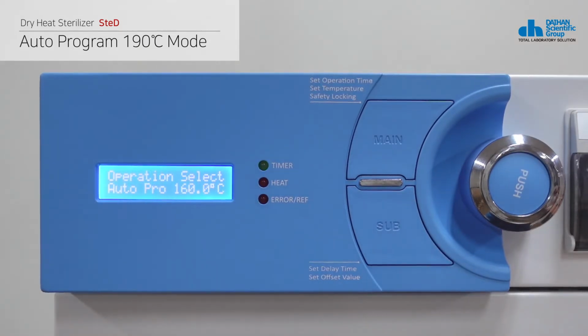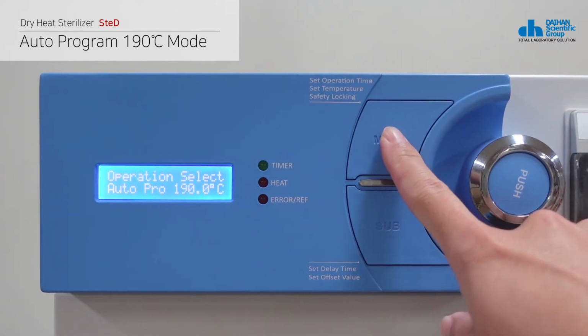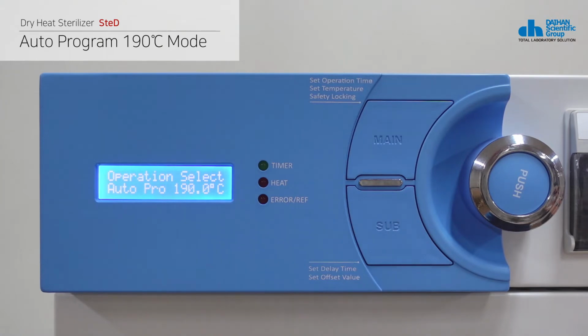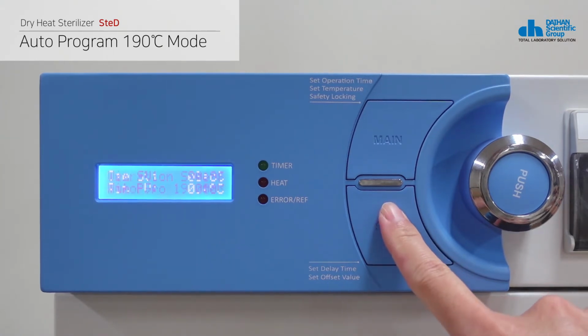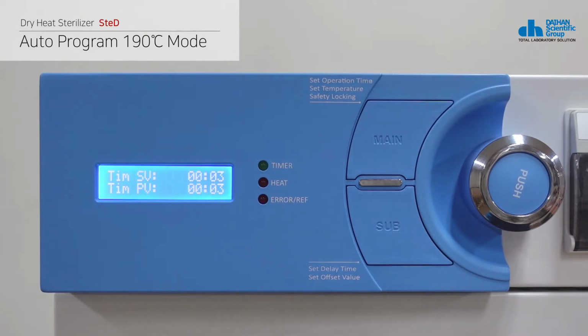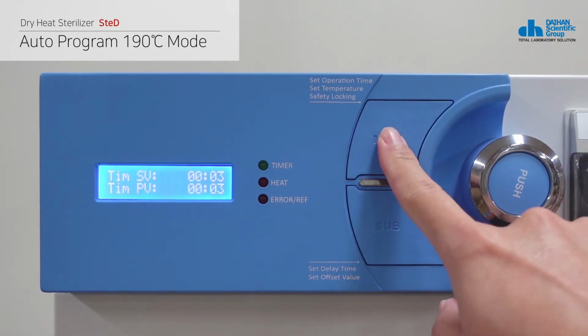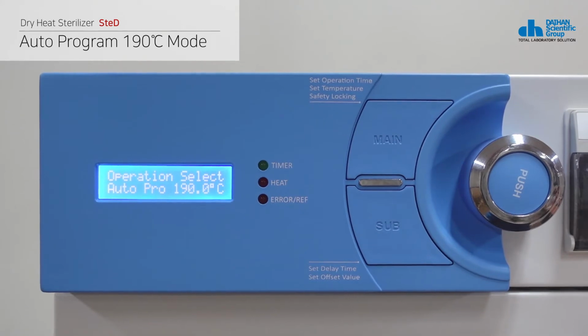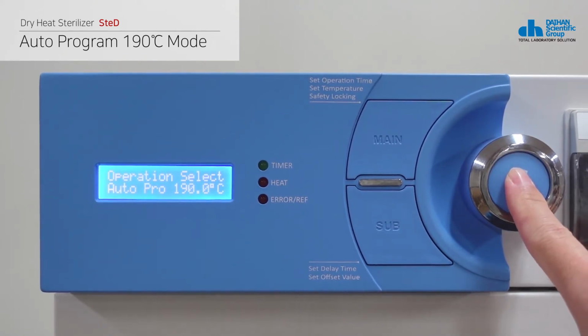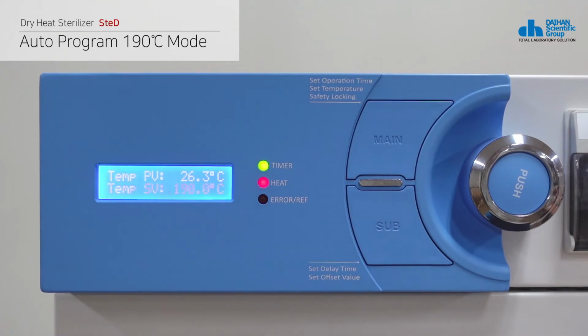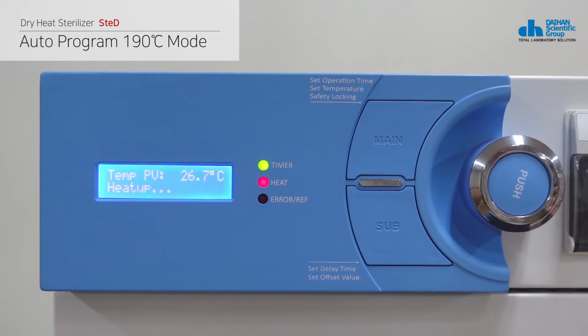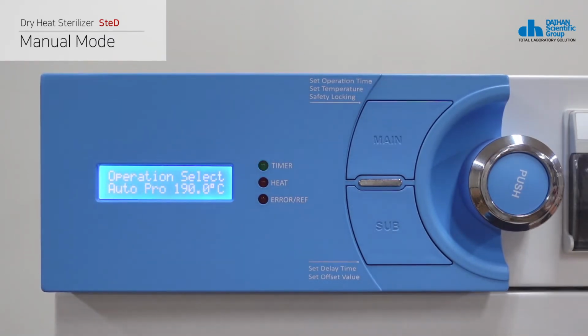In auto program 160 degrees Celsius mode, press the main button to switch to auto program 190 degrees Celsius. This mode automatically executes sterilization at 190 degrees Celsius for 3 minutes. Press the push button in the auto program 190 degrees Celsius mode and perform sterilization at 190 degrees Celsius for 3 minutes in the same order as in the 160 degrees Celsius mode. Press the main button in the auto program 190 degrees Celsius mode to switch to manual mode.